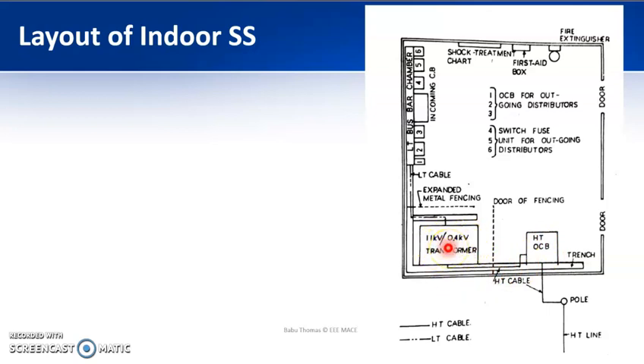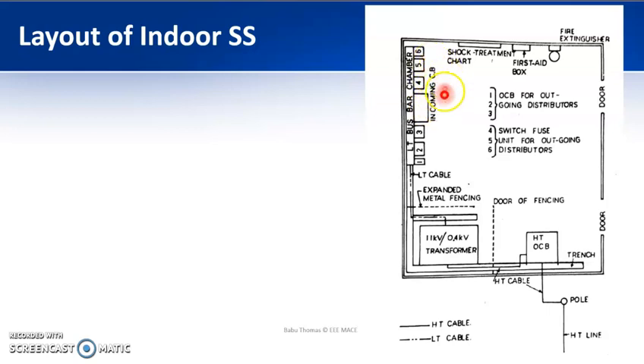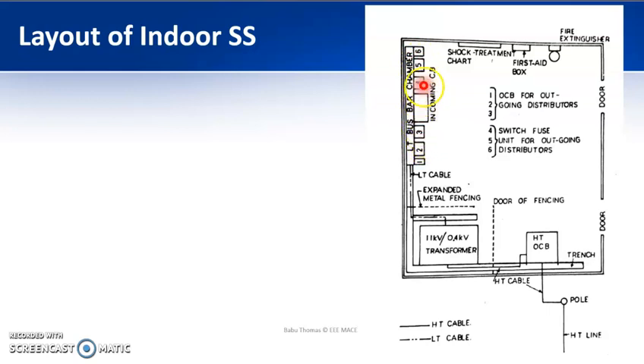From the transformer, the secondary bushings will be there and a three-and-a-half core cable runs to the LT bus bar chamber. Here you will have an incoming circuit breaker — if it trips, it will not provide power to any of the loads connected to the LT bus bar. The outgoing circuits, numbered one through six, use oil circuit breakers for outgoing distributors, varying depending upon the type of load connected.